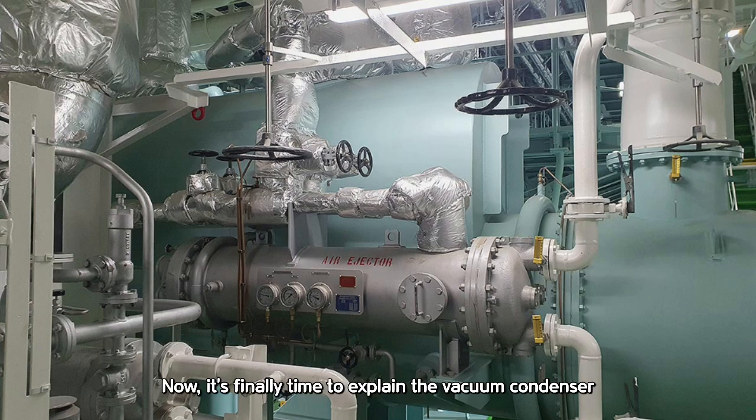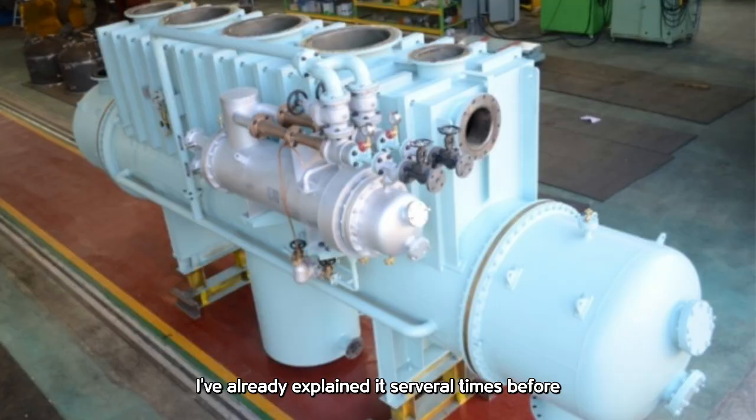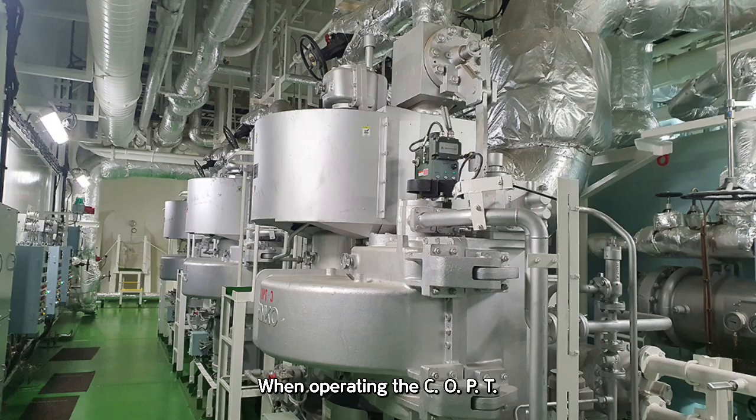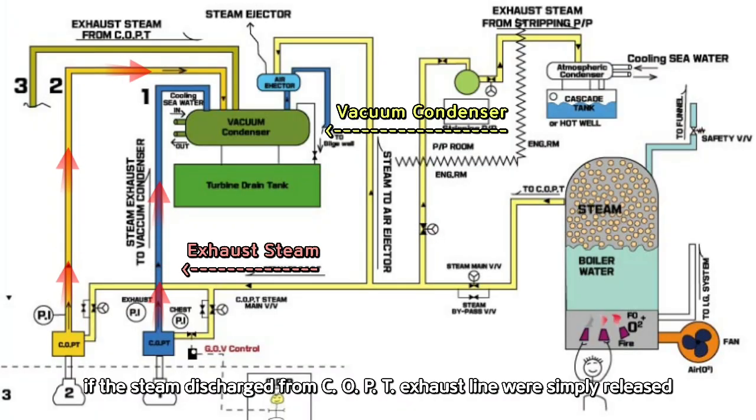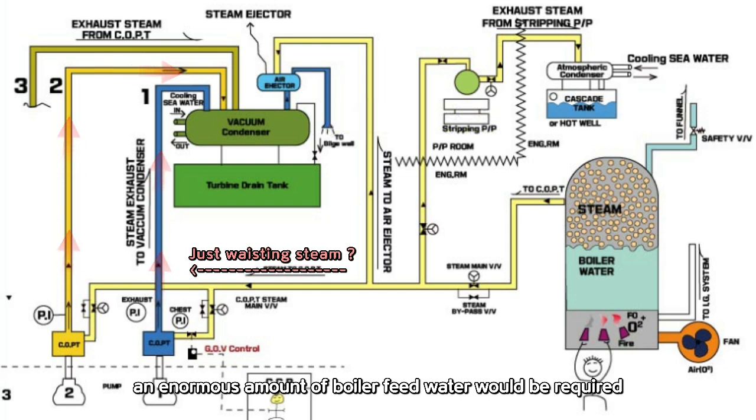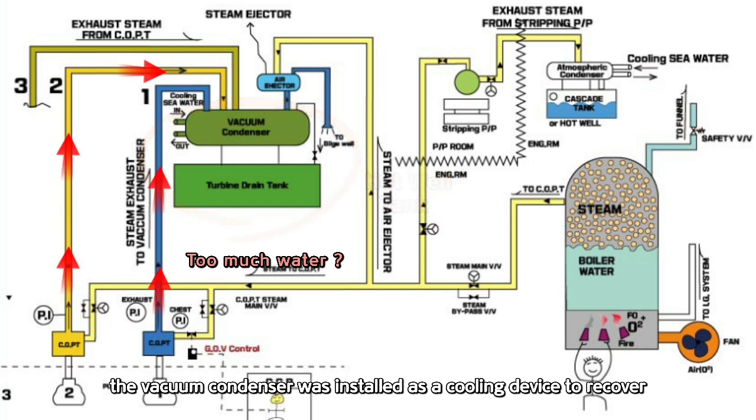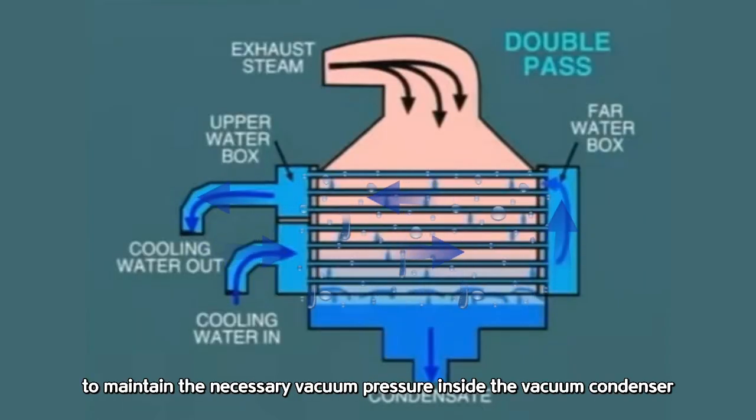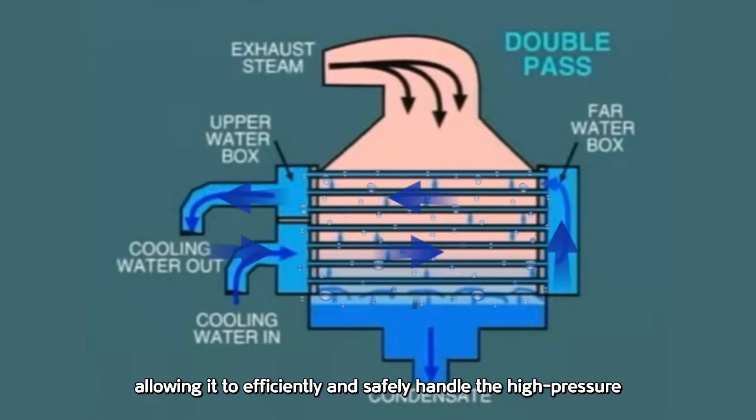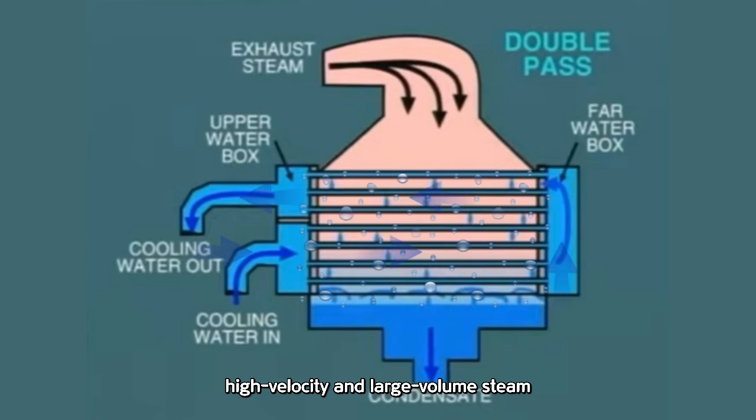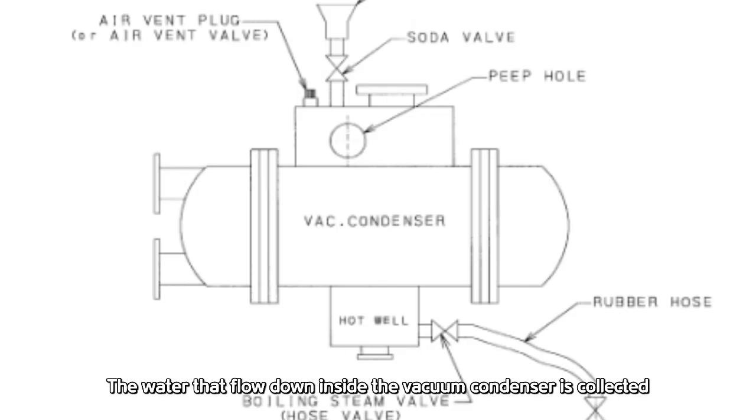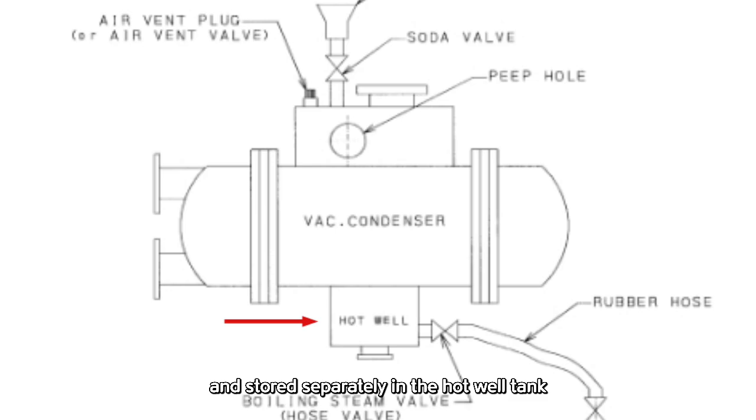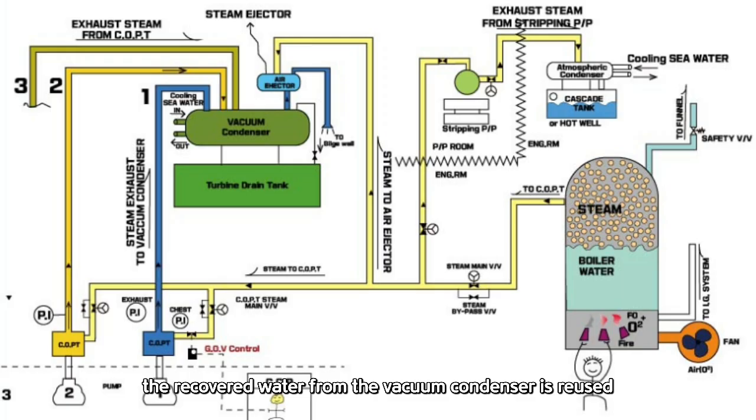Now it's finally time to explain the vacuum condenser, which is attached to the steam ejector like a parent and child. I've already explained it several times before, but let's go over it once more. When operating the COPT, if the steam discharge from COPT exhaust line were simply released, an enormous amount of boiler feed water would be required. To prevent this, the vacuum condenser was installed as a cooling device to recover and store the used steam, allowing it to be recycled as boiler feed water. When operating the COPT, the steam ejector is used to maintain the necessary vacuum pressure inside the vacuum condenser, allowing it to efficiently and safely handle the high pressure, high velocity, and large volume steam discharged from the COPT exhaust line. This system uses seawater for cooling, ensuring smooth and stable operation. When high temperature steam is cooled, it naturally condenses into water droplets. The water that flowed down inside the vacuum condenser is collected and stored separately in the hot well tank. Later, when additional boiler water is needed for the operating boiler, the recovered water from the vacuum condenser is reused.